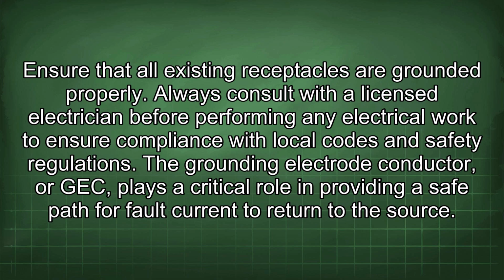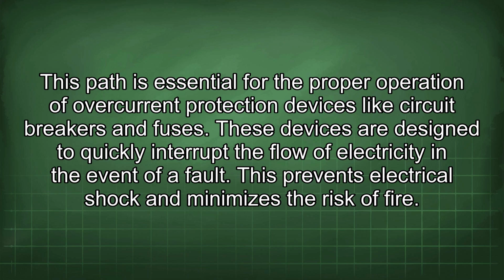The grounding electrode conductor, or GEC, plays a critical role in providing a safe path for fault current to return to the source. This path is essential for the proper operation of overcurrent protection devices like circuit breakers and fuses. These devices are designed to quickly interrupt the flow of electricity in the event of a fault. This prevents electrical shock and minimizes the risk of fire.